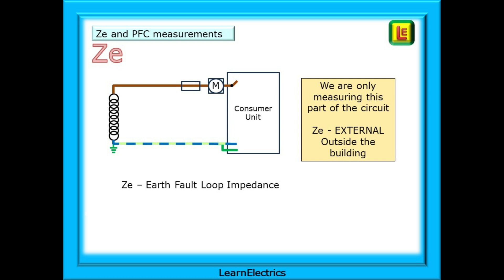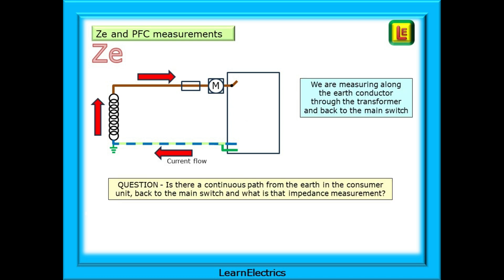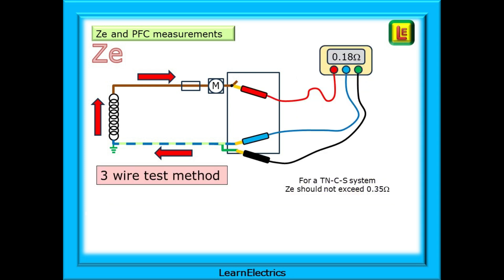We are only measuring this part of the circuit, ZE external to the installation, the outside of the building. We are measuring along the earth conductor through the supply transformer and back to the main switch. The question that we want answering asks is there a continuous path from the earth in the consumer unit all the way to the supply transformer and back to the main switch, and what is that impedance measurement? Why must the current path come back to the main switch you ask? Because without the current returning to the consumer unit and passing through the fuses, how are the fuses or circuit breakers ever going to blow and shut off the supply? The ZE test is a live test and you must show that you can work safely and isolate relevant parts of the circuit.